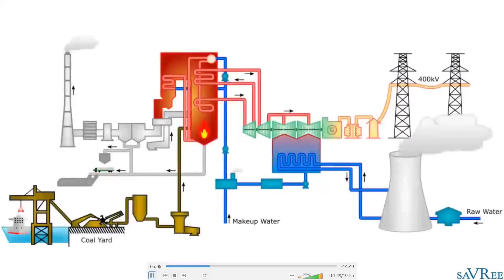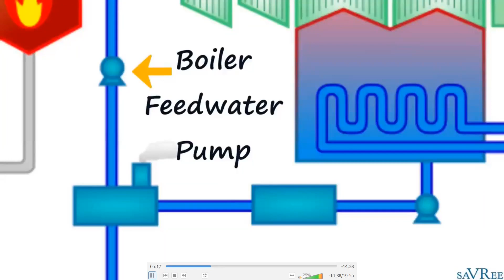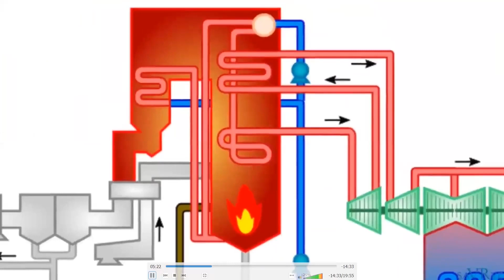Then we'll go to a boiler feed water pump. This is usually a multi-stage centrifugal pump, and we will increase the pressure. This boiler feed water pump will consume a significant amount of energy. It can be as high as 5% of the power produced by the turbine. Usually they're huge pumps and require a tremendous amount of energy. We increase the pressure of our boiler feed water and send it to our water tube boiler. The pressures involved here are actually quite high. You're looking at in excess of 200 bar, which is in excess of around 3000 psi.